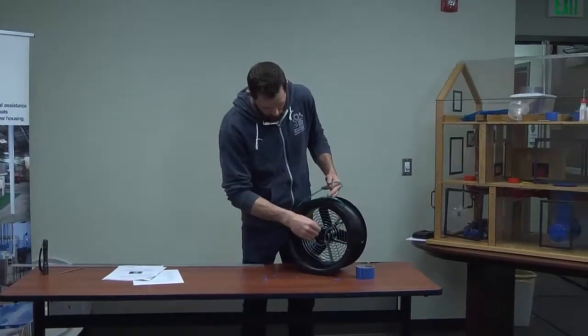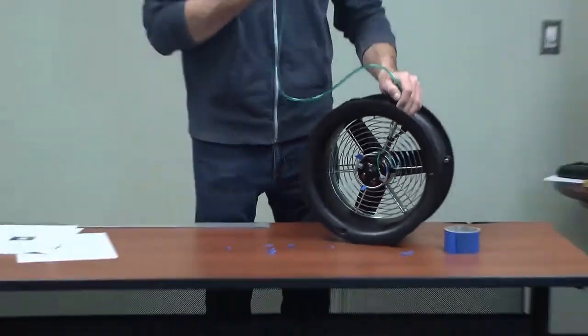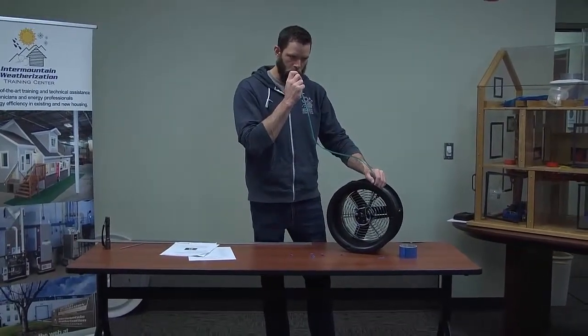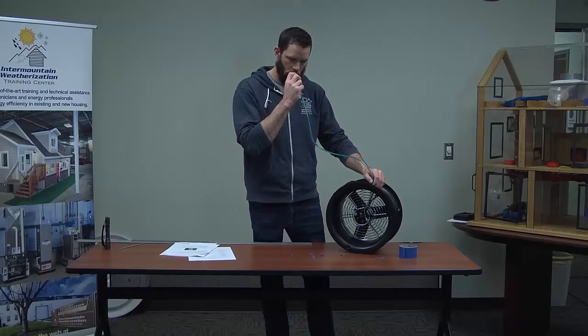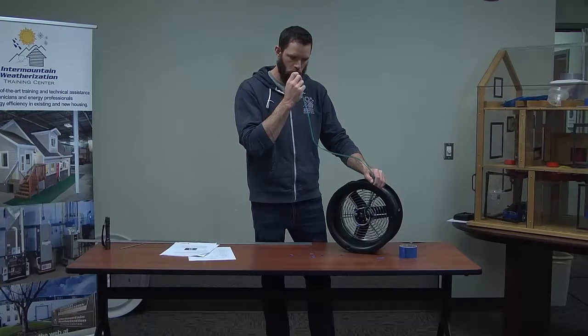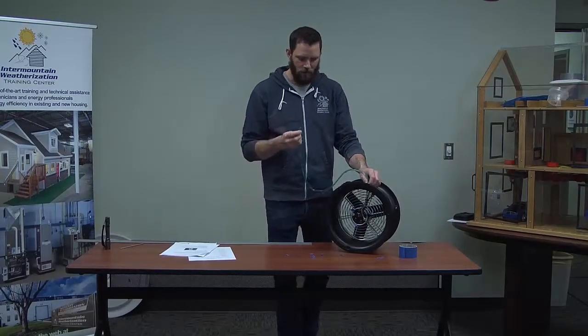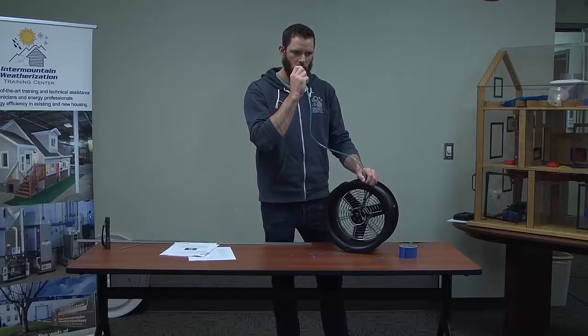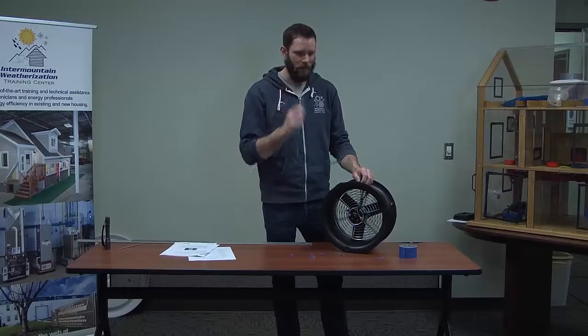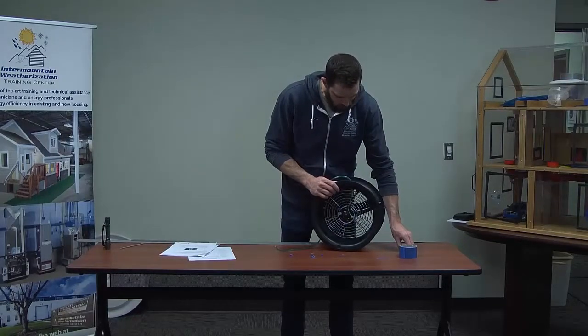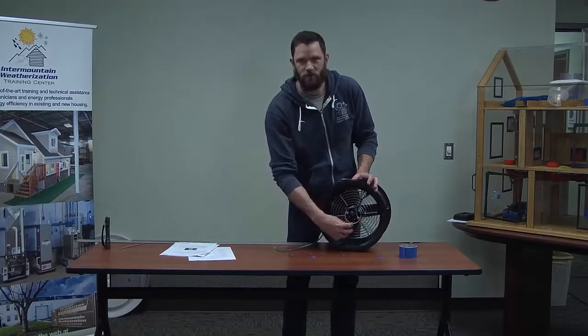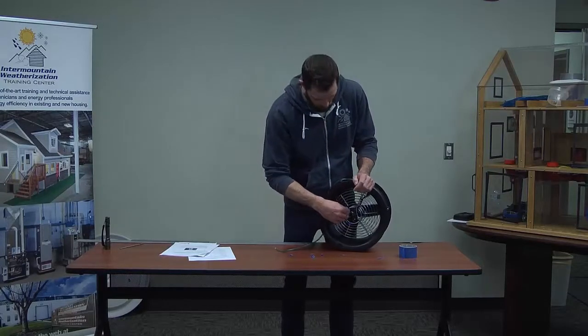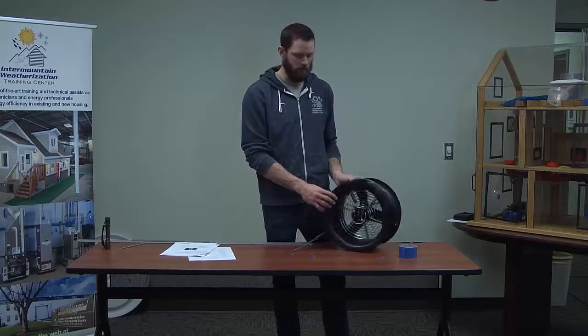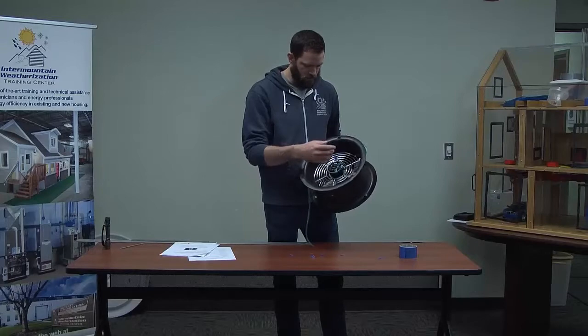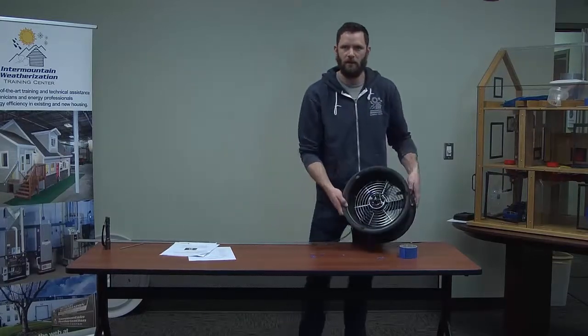Okay, so I got it taped off, got my hose hooked up to the flow port, and I'm going to put a vacuum on this. Yep, I just did it a couple times there, but it is holding now. I don't know if you can hear that, but it kind of pops as I come off. So what had happened the first time that I tried it, I had too wide of strips of tape, so it wasn't quite sealing off the holes. And so I went through and made thinner strips of tape that actually helped seal it off. So from my visual inspection and the leakage test, this one passes that test.